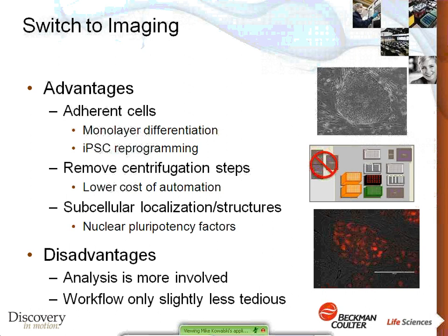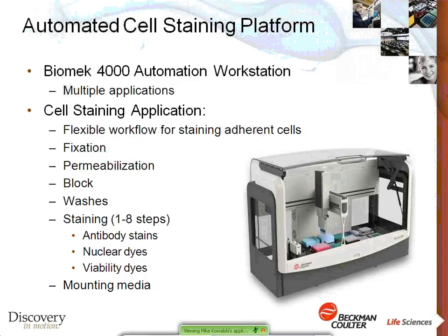Disadvantages of imaging include slightly more involved analysis and a workflow that still has many buffer exchanges and antibody changes. That's why we automated this process using our Biomek 4000 automation workstation — a flexible platform for our cell staining application, designed to automate all steps: fixation, permeabilization, blocking, multiple washes, multiple staining steps — whether antibodies, nuclear dyes, or viability dyes — and even adding mounting media at the end. The software is designed to be as easy and flexible as possible. You select a sample pattern, choose staining permutations, fix or permeabilize or skip these steps for live staining, choose one to eight staining steps, and set your final processing in PBS or mounting media.